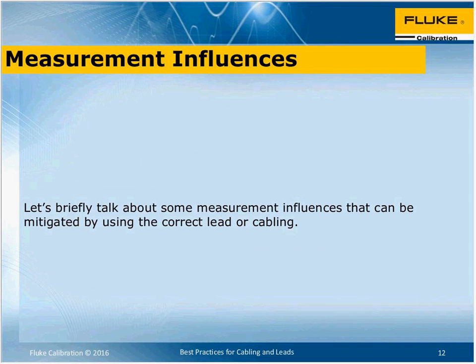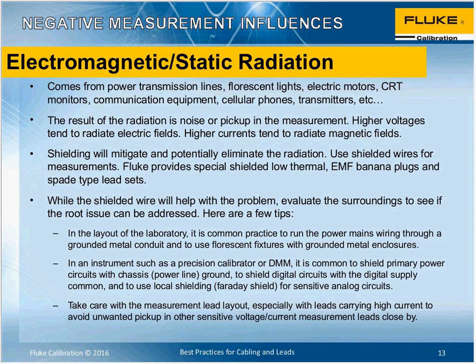Okay, great. So I'm going to turn it over to Paul, and Paul's going to talk about measurement influences. Hey, thanks, Rich. Yeah, we're going to talk about a number of influences, and then talk about what we can do in terms of the leads we might use and the way we might use those leads to reduce some measurement problems. But one thing you really should think about first is trying to eliminate the sources of any potential problems and interference, rather than concentrating on the best possible lead to avoid the influence that's there. We should do both. We should obviously use the best possible lead, but really should make sure that we choose the right environment and conditions such that we don't have the influences in the first place.